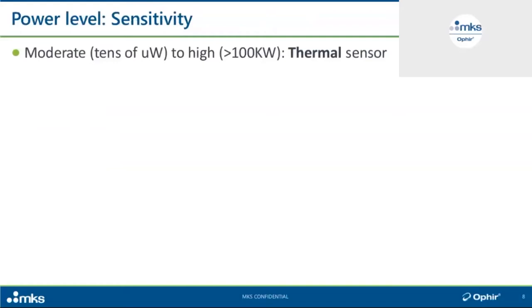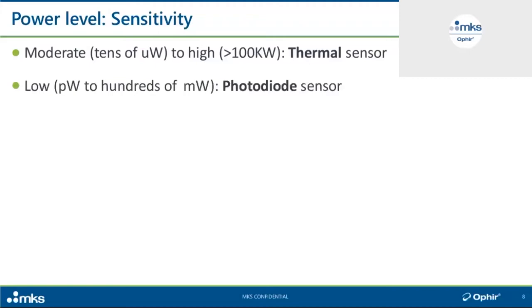Regarding power level and sensitivity: typically for measuring powers from tens of microwatts and upwards, one uses a thermal sensor. At Ophir, we have thermal sensors that can go down to 8 or 10 microwatts, which is quite sensitive for this type, and a thermal power sensor that can measure up to 120 kilowatts. For lower powers — down to picowatts and nanowatts, up to hundreds of milliwatts — we typically use a photodiode sensor, which is much more inherently sensitive than thermal sensors.